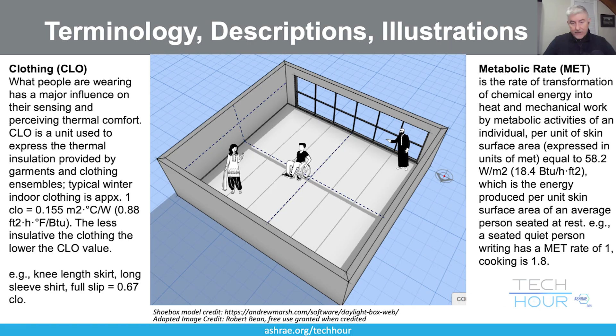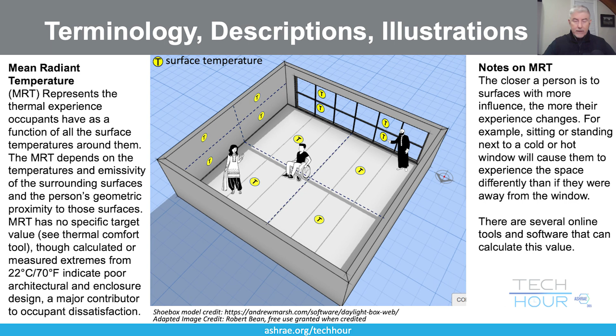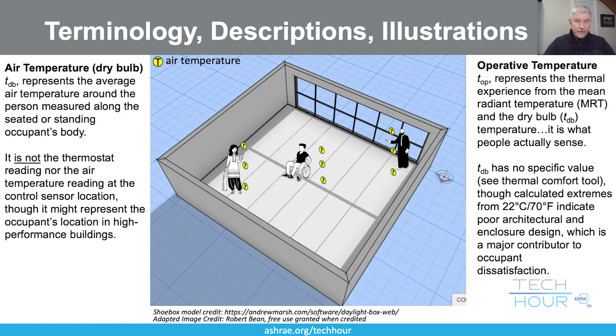So the proximity that people have to dominant surface temperatures is going to have a much stronger impact on their experience. So this mean radiant temperature is incredibly important. We also want to acknowledge the role that air temperature plays, but the air temperature that we're referring to in the standard is actually the air temperature around the occupant, not what is read on the thermostat. And collectively, when we marry air temperature and mean radiant temperature together, we achieve what's called the operative temperature. We also want to look at the air velocity, that is the speed of the air flowing across the occupant. It's not the air coming out of the diffuser or in the duct itself, but in fact the airspeed across the body.